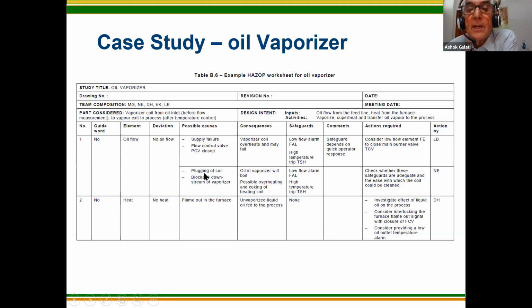What happens with this deviation, what is the consequence? The vaporizer coil will overheat and may fail, because burning of the fuel is taking place but no oil is flowing within the pipeline. So there will be overheating of the pipeline and it will fail. Oil in the vaporizer will boil, whatever little bit there is, with overheating and coking. When oil boils, it actually forms coke. Coke will deposit on the pipeline. So that is also going to result.